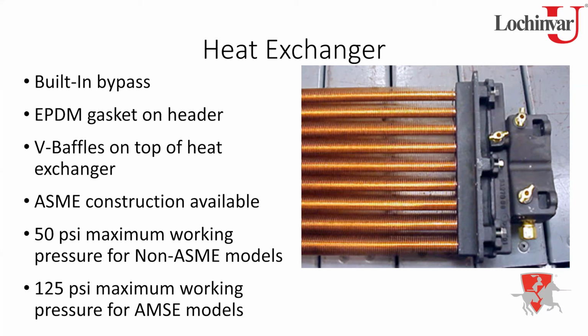If for some reason you overpressurize the heat exchanger, or if you've got an issue that's going to create a leak, it's typically going to be at the gasket, which also means that it is replaceable. So you can pull that head off and replace the gasket if you need to. And that's always a good point. Now in saying that, it is the only gasket that's involved with this heat exchanger. As far as where the copper tubes go into the cast header and footer, those copper tubes are actually swedged into that cast header and footer. So there's no gasket in that area.